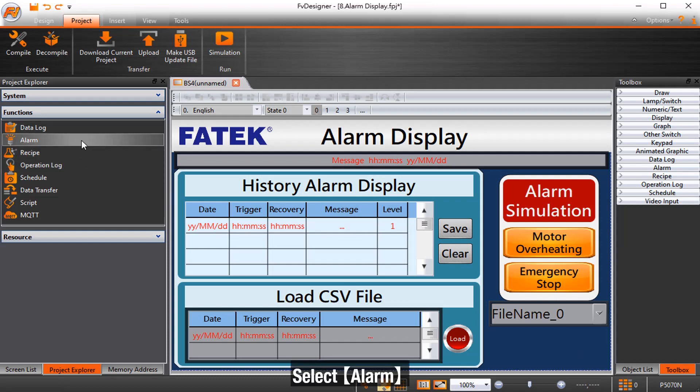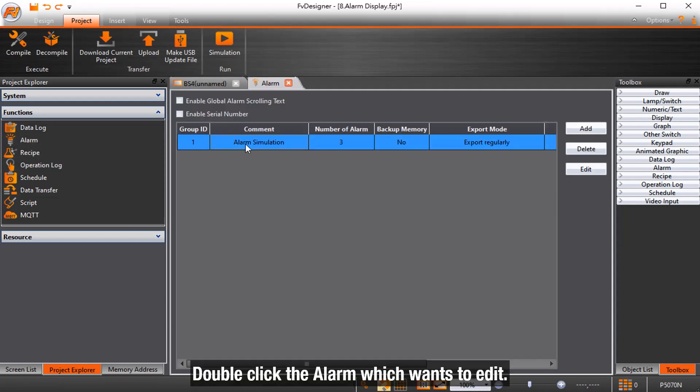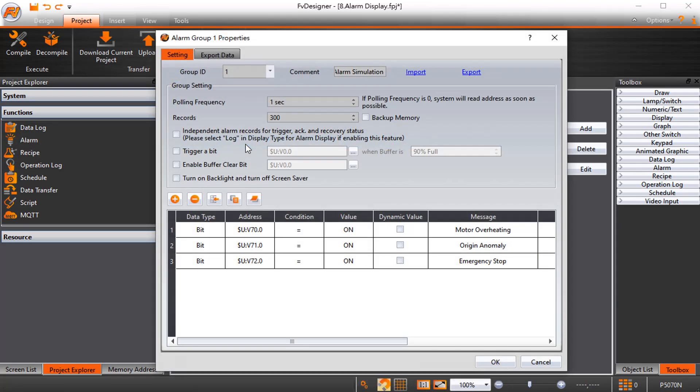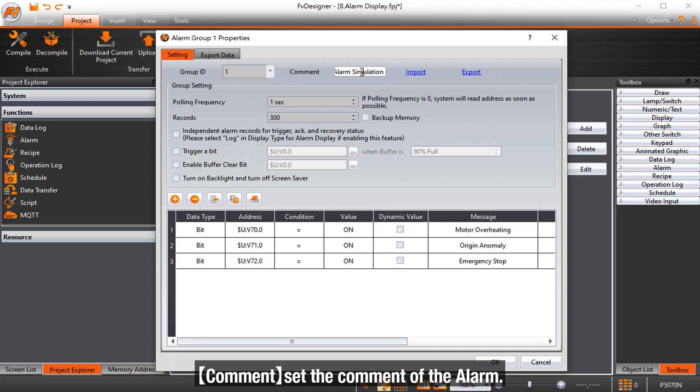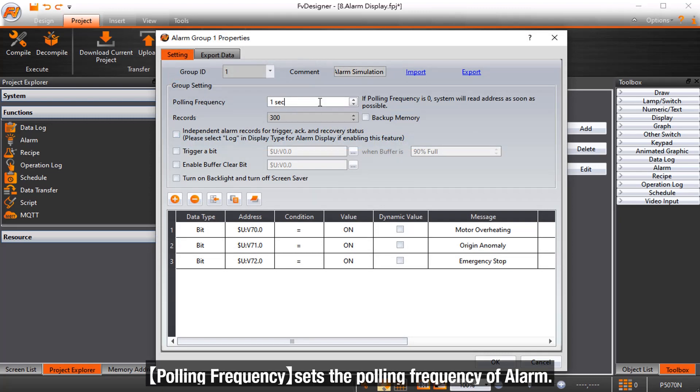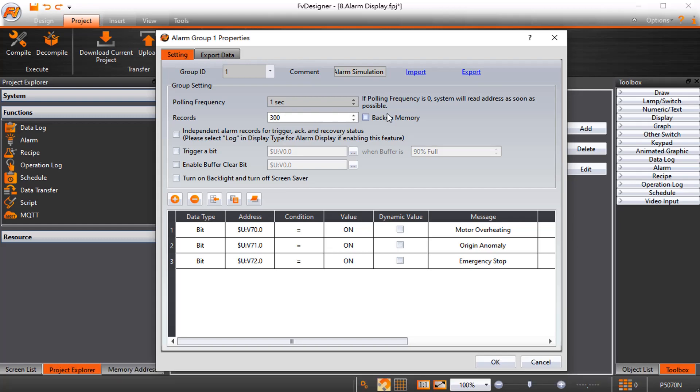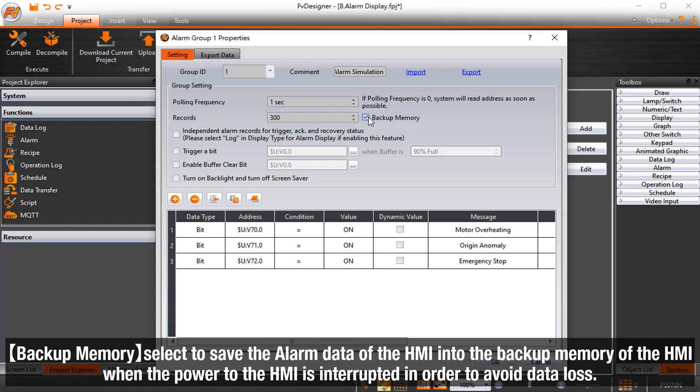Select Alarm. Double-click the alarm which you want to edit. Comments set the comment of the alarm. Polling frequency sets the polling frequency of alarm. Record sets the maximum number of alarms to save for the current alarm group. Backup memory, select to save the alarm data of the HMI into the backup memory of the HMI when the power to the HMI is interrupted in order to avoid data loss.